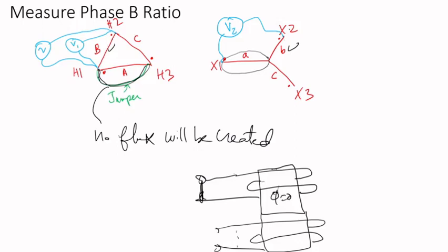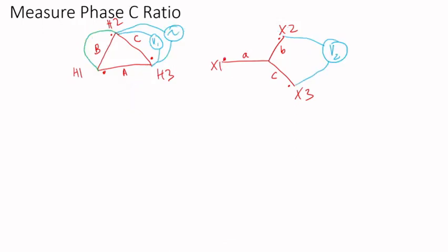Then I'm measuring from X2 to X1, but X1 is just connected to the neutral. So it's as if I'm measuring from X1 to here. That's what I'm doing. Then I can do the same thing for phase C. I want to measure phase C. Phase C is here, then phase C is here, so these two are parallel. But the problem is, for instance, I'm going to measure from X3 to X2, so I have to short this here.